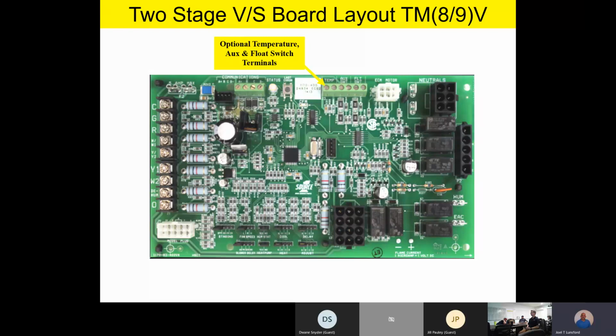Well, you don't have to take any wires off or break any wires with this. So if you have a communicating system, you can hook up an accessory float switch. For instance, this is just one of the things you can hook up. Hook up an accessory float switch. It'll go ahead and tell the board that you've got a condensate issue or a float switch issue. So you've got some optional terminals there if you're running a communicating system.